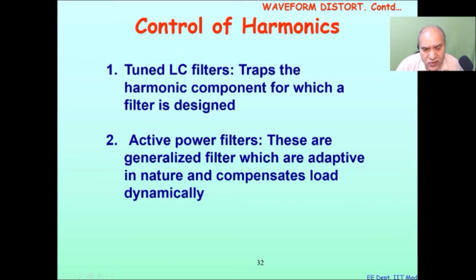Tuned LC filters, you might know this kind of filter, which you also use for analog circuits, but this is for power circuits. Therefore, the current and voltage rating is quite high as compared to analog filters. But the concept is the same: you have to trap the harmonic component for which the filter is designed. The problem with the tuned filter is that you have to use a number of filters, one for each frequency to be trapped. Hence, the problem of bulkiness arises in these applications.